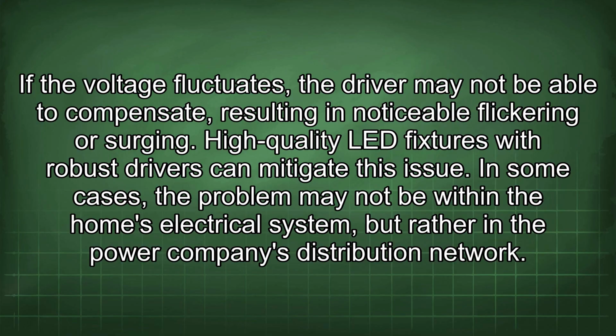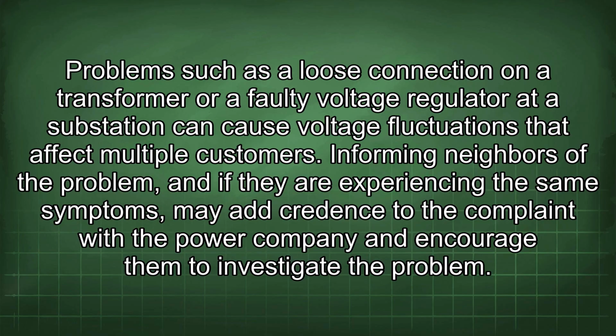In some cases, the problem may not be within the home's electrical system, but rather in the power company's distribution network. Problems such as a loose connection on a transformer or a faulty voltage regulator at a substation can cause voltage fluctuations that affect multiple customers. Informing neighbors of the problem, and if they are experiencing the same symptoms, may add credence to the complaint with the power company and encourage them to investigate the problem.